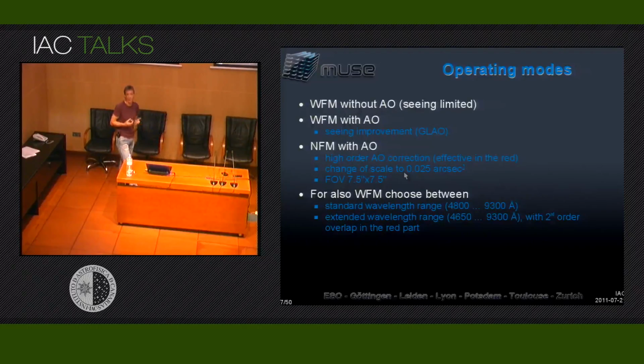And then there's the narrow field mode, which can only be used, or only makes sense to be used, with AO, which will have high order AO correction, which will be mostly effective in the red part of the spectrum. It just works that you change the spatial scale of the instrument so that you sample not with 0.2 arc seconds, but 0.025 arc seconds. And you get a field of view of 7.5 by 7.5 arc seconds.